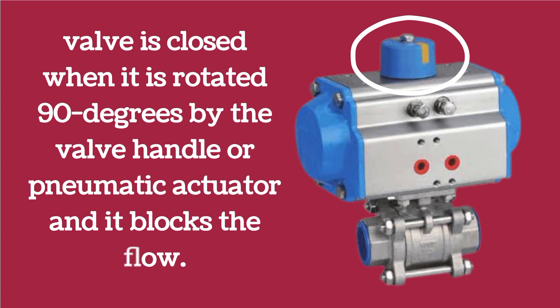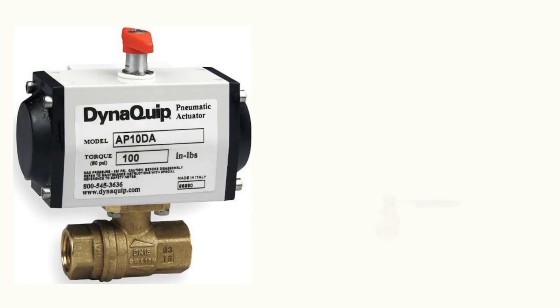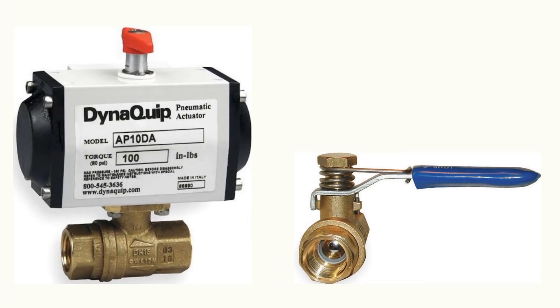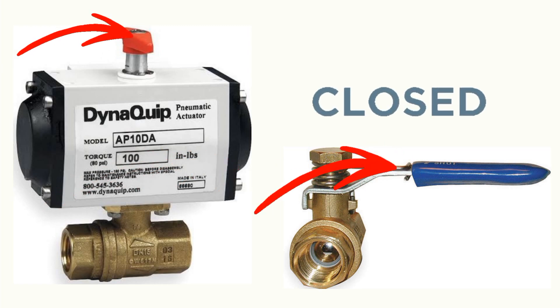In this case, the valve actuator position will be perpendicular to the pipeline. So remember: when the indication is in line, the valve is open, and when the indication is perpendicular, the valve is closed. In these images, the actuators are in closed position as they are perpendicular to the valve.